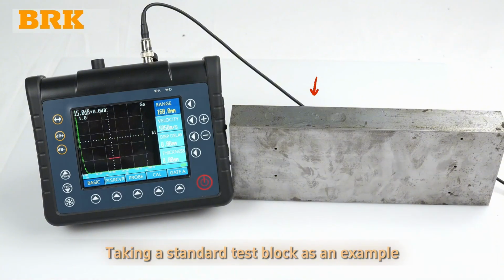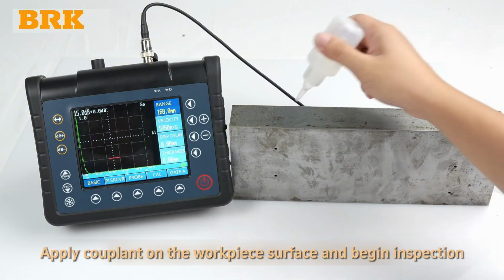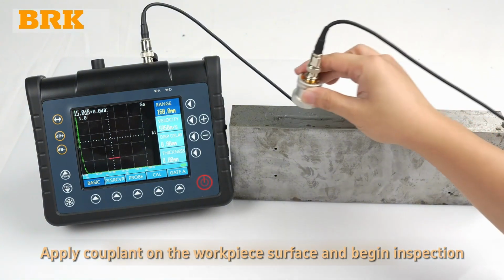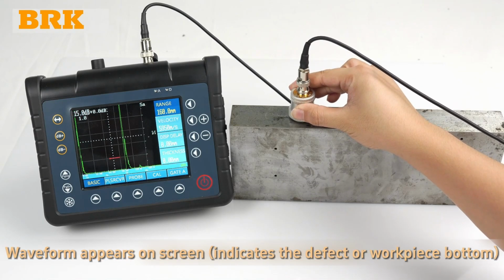Taking a standard test block as an example, apply couplant on the workpiece surface and begin inspection. Waveform appears on screen indicates the defect or workpiece bottom.